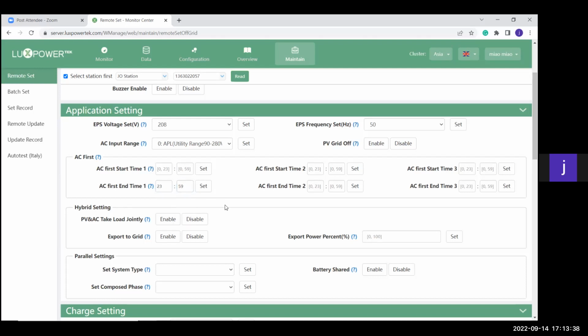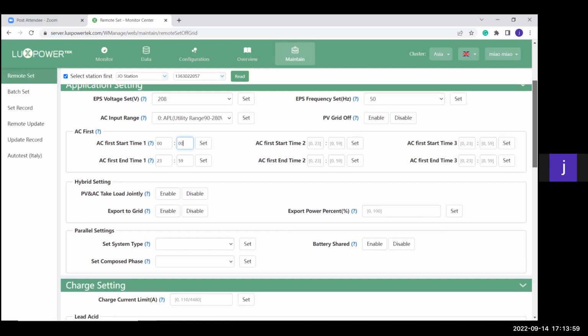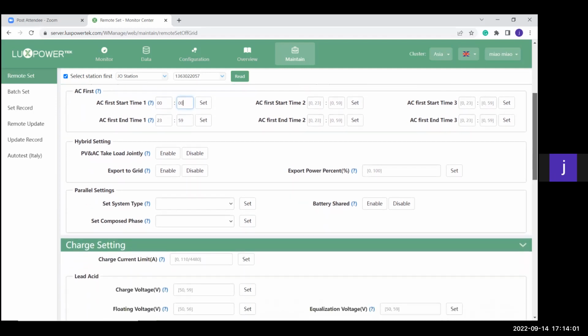2359 at that moment. And then you press the set button and it will set it at 2359. The other values I don't use. I only use the AC first start time 1. The other ones are not necessary, and the start will be 0000. So that basically tells the machine that it will be active 24/7 on AC first.